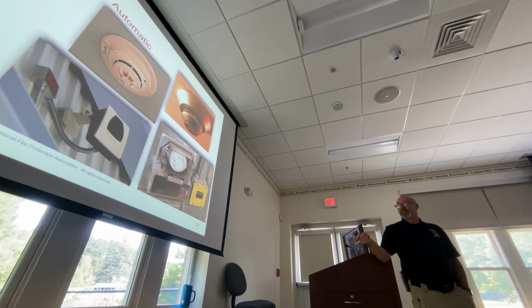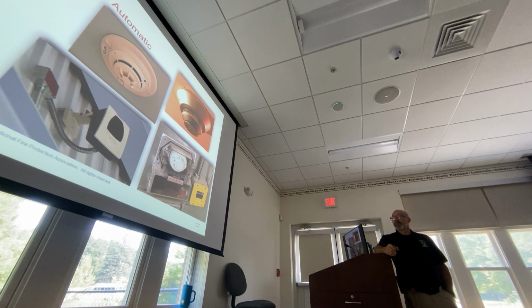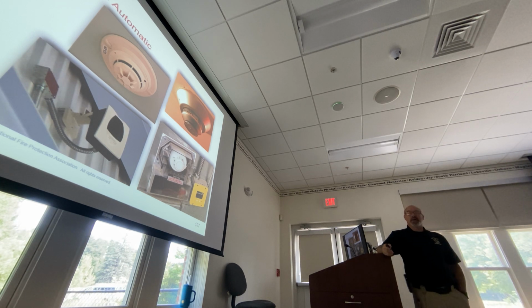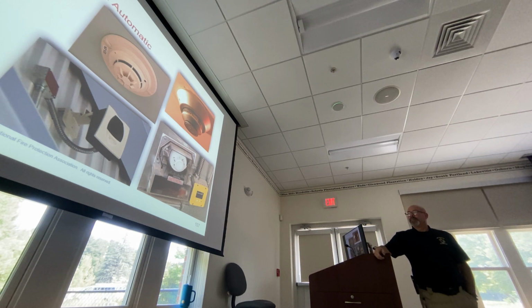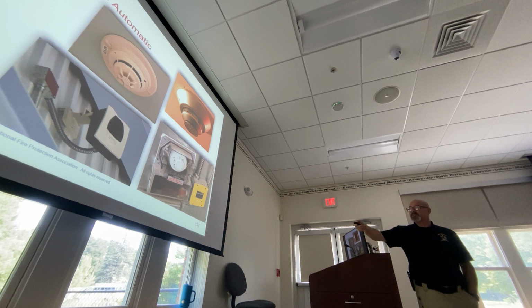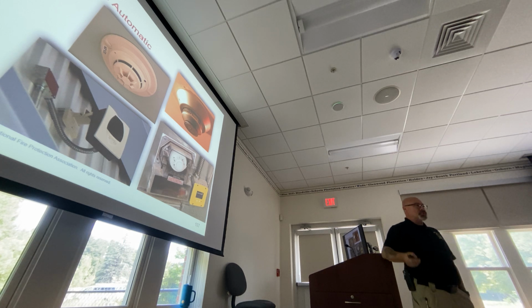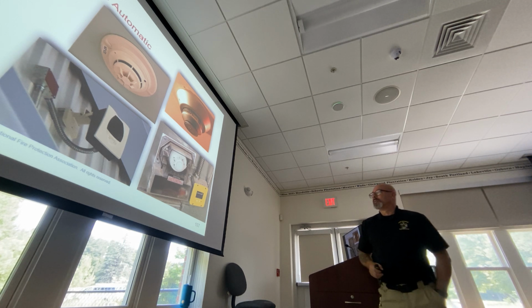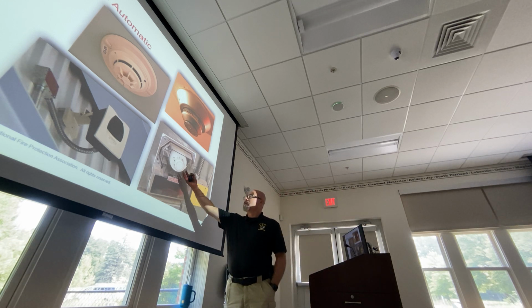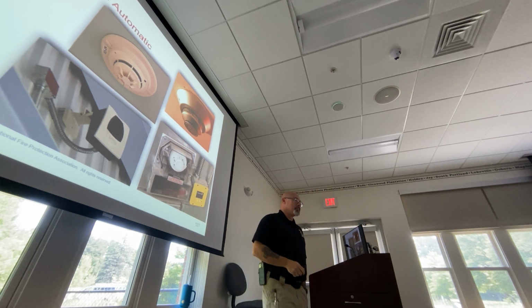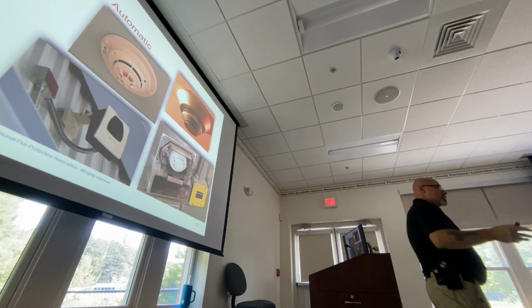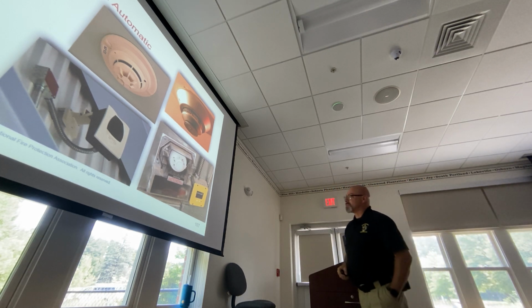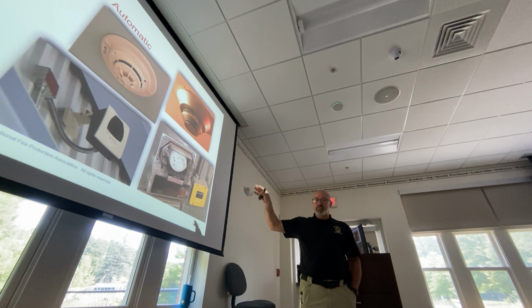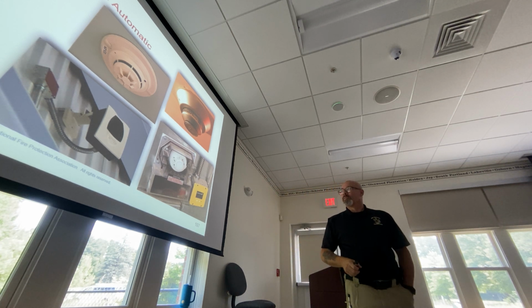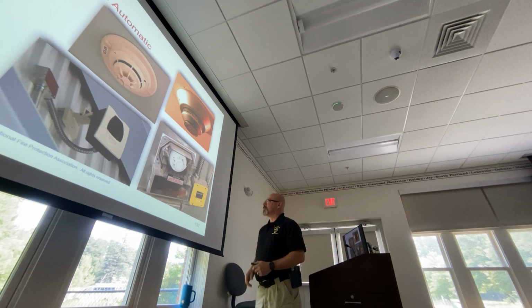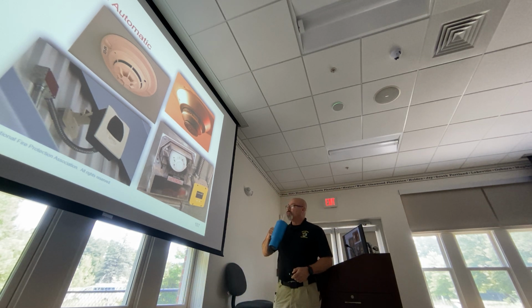How about this one? What's this? HVAC smoke. Yep, a duct detector. That duct detector is actually in duct work. It has a sensor, a probe that goes in, and it actually sniffs every so often to check. And if it senses smoke, if it pulls smoke into it, it goes into an alarm. Rooftop units, RTUs. If you look at a control panel on a fire alarm system, you'll see RTU1, RTU2, RTU3. Rooftop units, oftentimes. Or duct 1, duct 2.